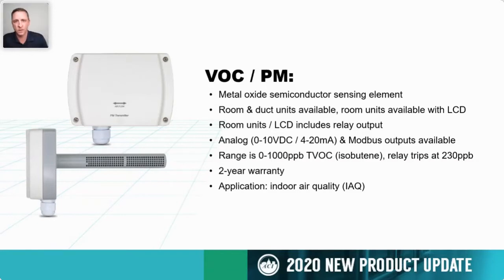That's total volatile organic compounds. While saying they're VOC, some sensors are outputting a 0 to 2,000 ppm equivalent of CO2. So on those types of sensors, they're using VOC to try to calculate a CO2 equivalent to be used in demand control ventilation, or to be used as a measure of occupancy in a certain space. Our device is giving you the true or total VOC output.